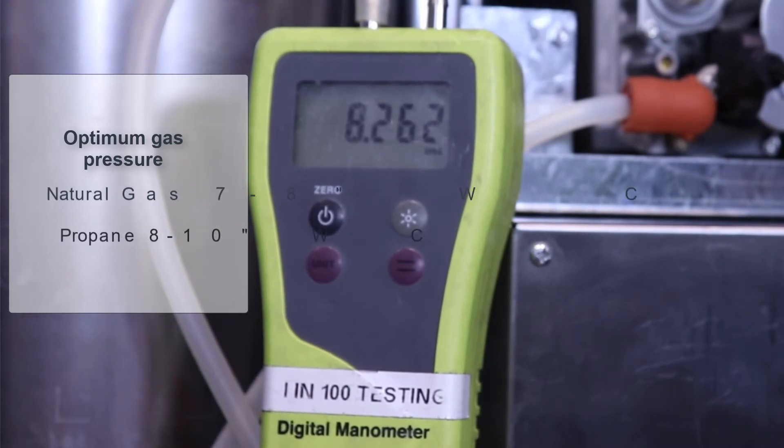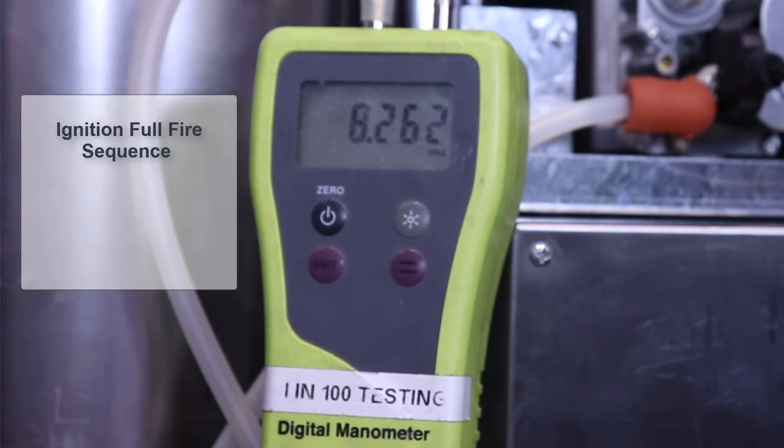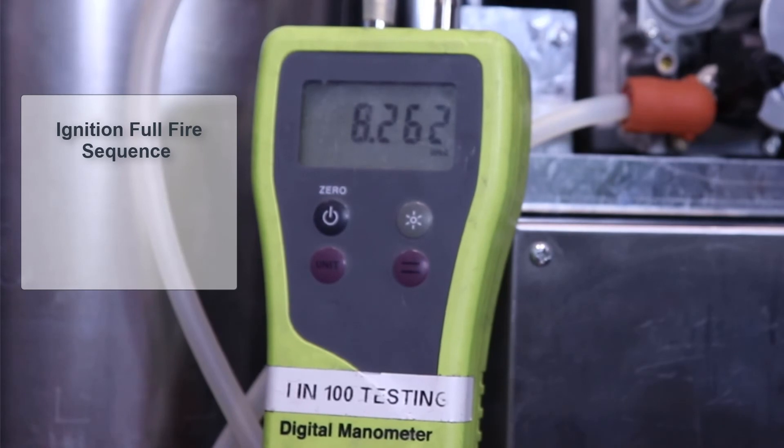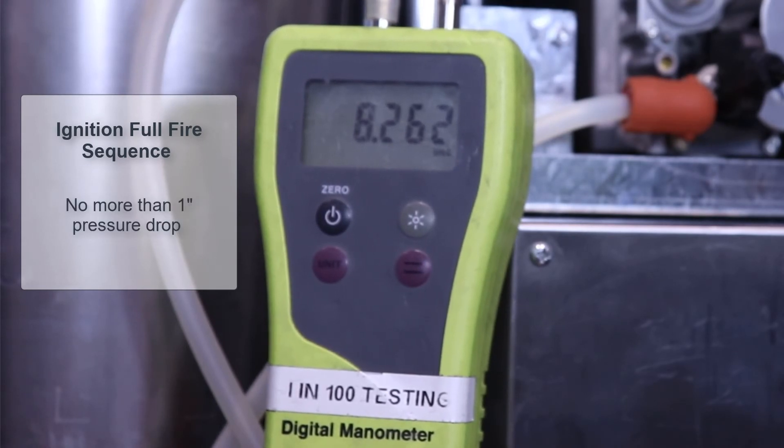During the ignition and full fire sequences of the boiler, we'd like to see no more than one inch pressure drop during these operational phases of the boiler.